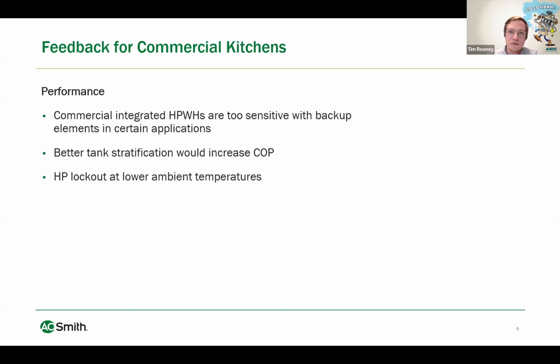There have been some cases where there's an unexpectedly large amount of backup element use, and we want to make sure in the future that these products' backup elements are truly backup elements. We've also seen from some third-party lab testing that there's room to improve our tank stratification strategy, and Amin alluded to this earlier. There are some scenarios where the heat pump can lock out when the room gets too cold.